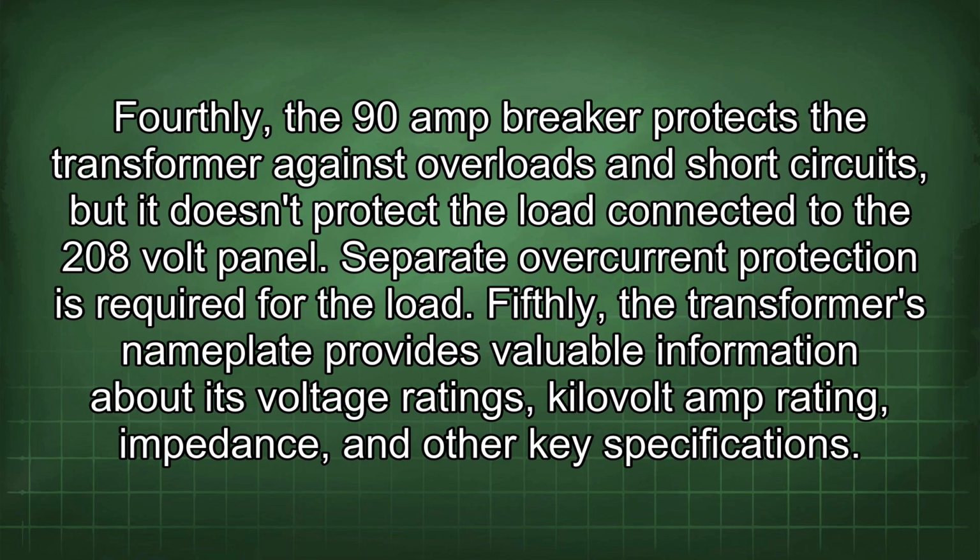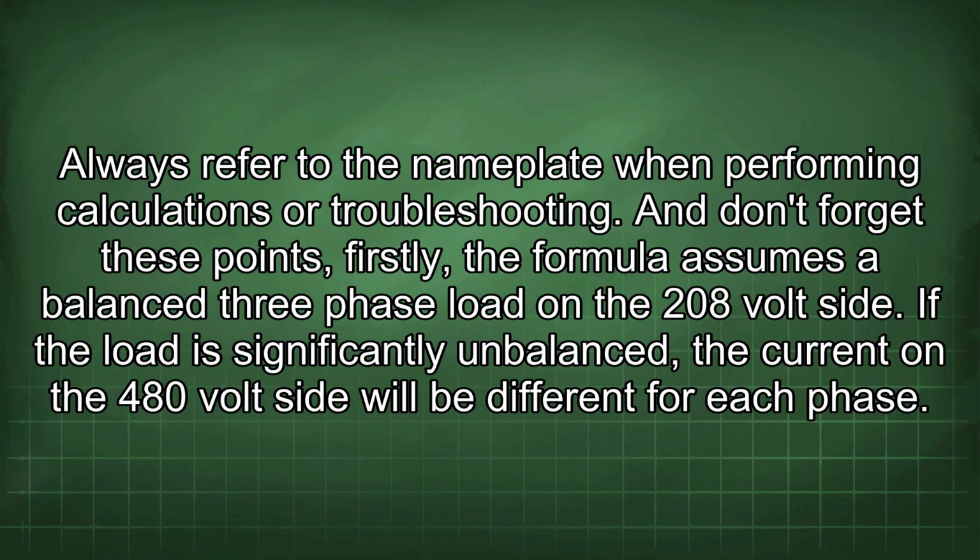Fourthly, the 90-amp breaker protects the transformer against overloads and short circuits, but it doesn't protect the load connected to the 208-volt panel. Separate overcurrent protection is required for the load. Fifthly, the transformer's nameplate provides valuable information about its voltage ratings, kilovolt amp rating, impedance, and other key specifications. Always refer to the nameplate when performing calculations or troubleshooting.